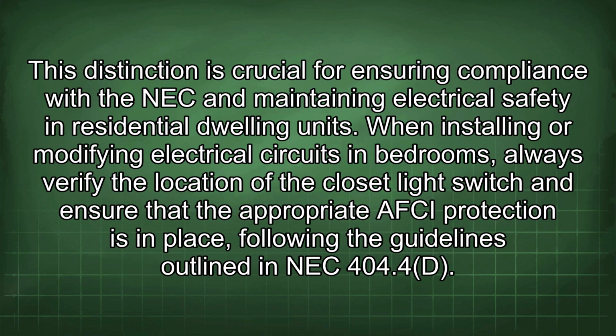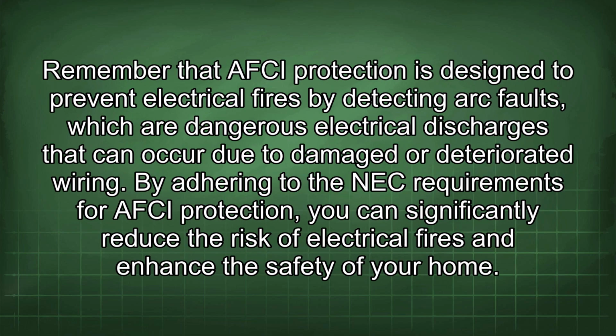This distinction is crucial for ensuring compliance with the NEC and maintaining electrical safety in residential dwelling units. When installing or modifying electrical circuits in bedrooms, always verify the location of the closet light switch and ensure that the appropriate AFCI protection is in place, following the guidelines outlined in NEC 404.4D. Remember that AFCI protection is designed to prevent electrical fires by detecting arc faults, which are dangerous electrical discharges that can occur due to damaged or deteriorated wiring. By adhering to the NEC requirements for AFCI protection, you can significantly reduce the risk of electrical fires and enhance the safety of your home.